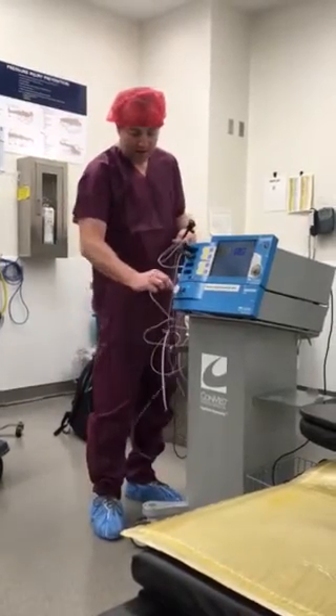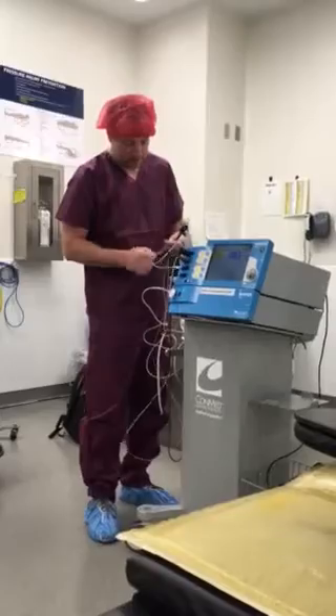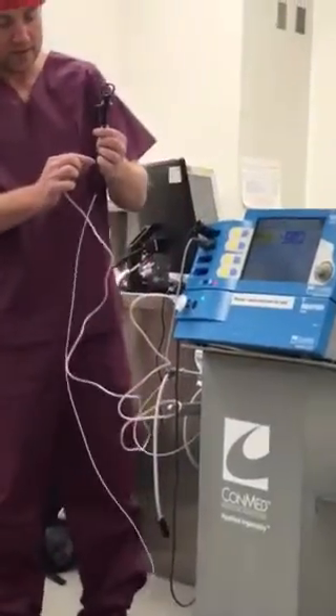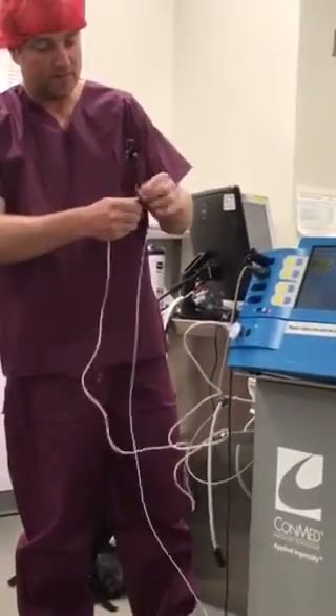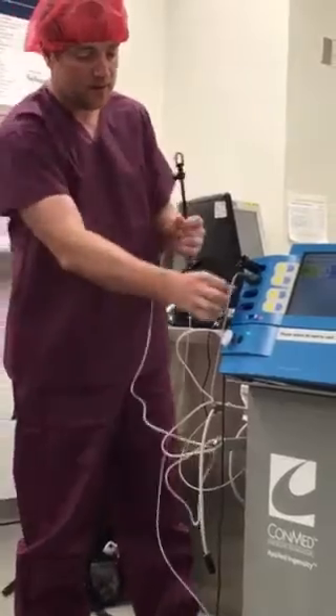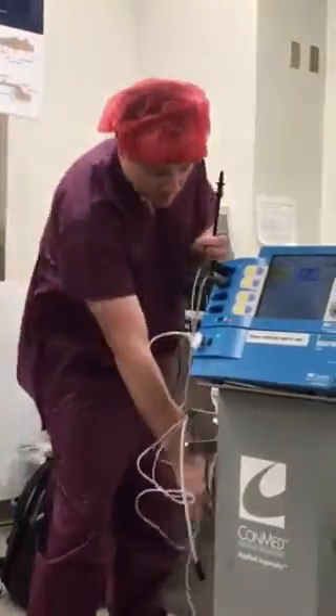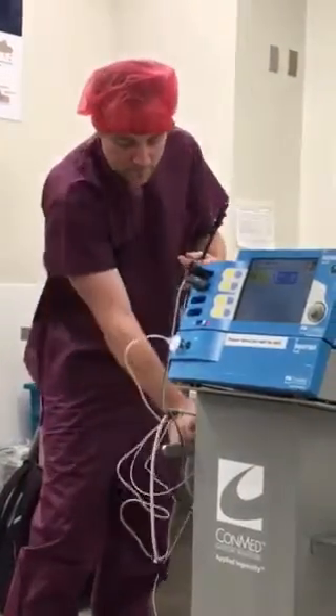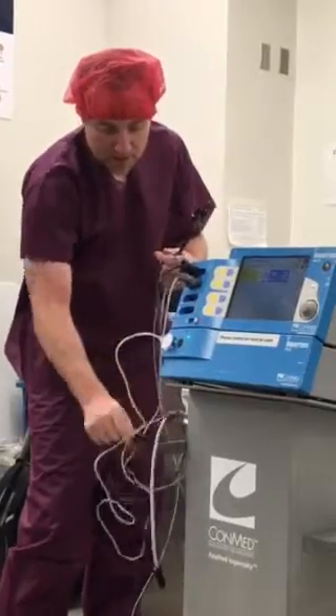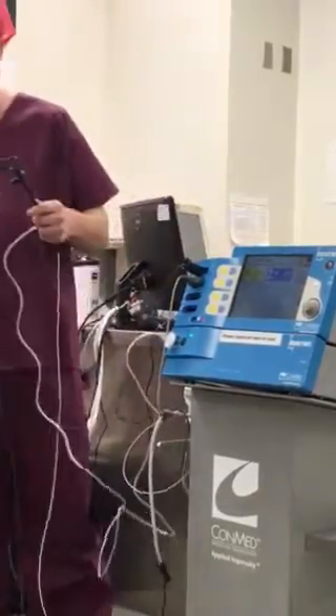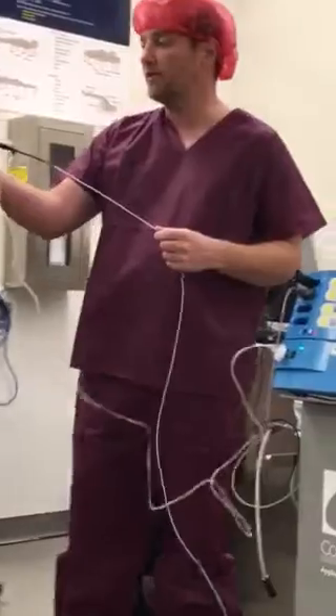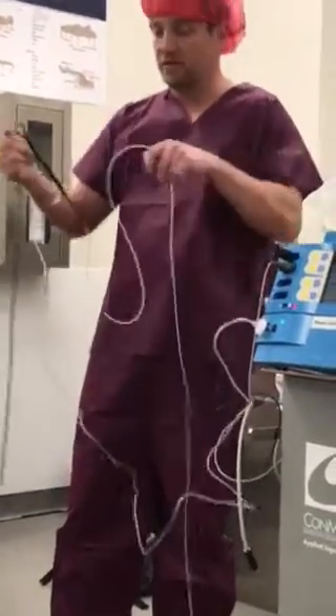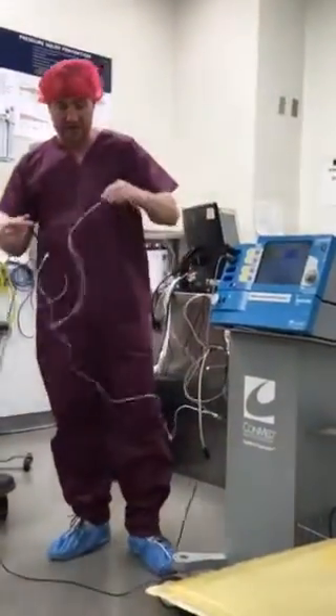The gas line is really just a simple luer lock into there, and then this is going to plug right into the bottom of the probe. And this is going to put the gas into the probe, and then the top part, you're just going to take the monopolar active cord, and you're going to plug the monopolar active cord into the top part like that, and it's going to go in and make a little snapping sound. That means it's connected properly.